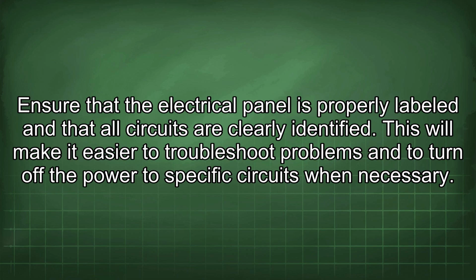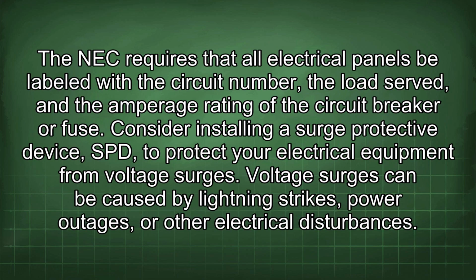This will make it easier to troubleshoot problems and to turn off the power to specific circuits when necessary. The NEC requires that all electrical panels be labeled with the circuit number, the load served, and the amperage rating of the circuit breaker or fuse.